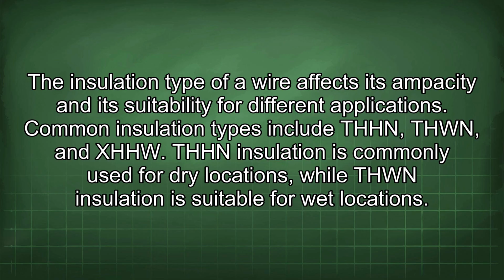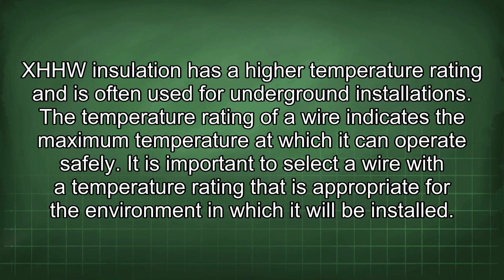The insulation type of a wire affects its ampacity and its suitability for different applications. Common insulation types include THHN, THWN, and XHHW. THHN insulation is commonly used for dry locations, while THWN insulation is suitable for wet locations. XHHW insulation has a higher temperature rating and is often used for underground installations.